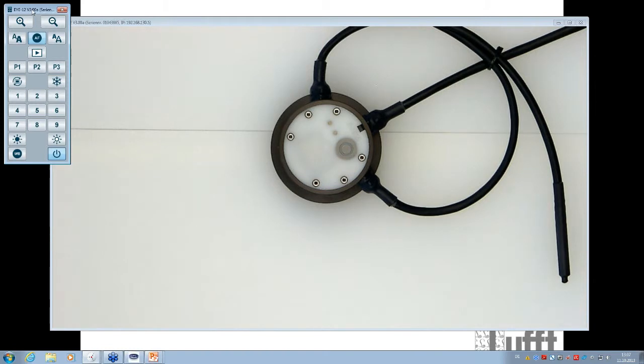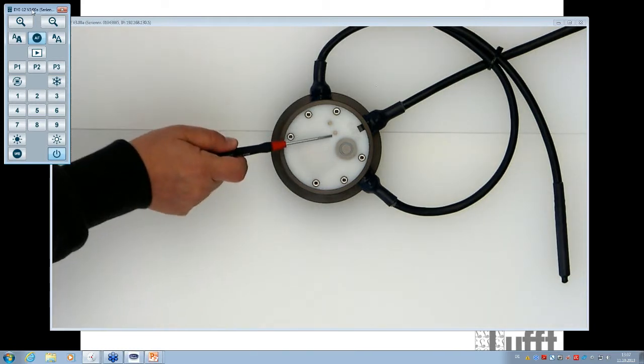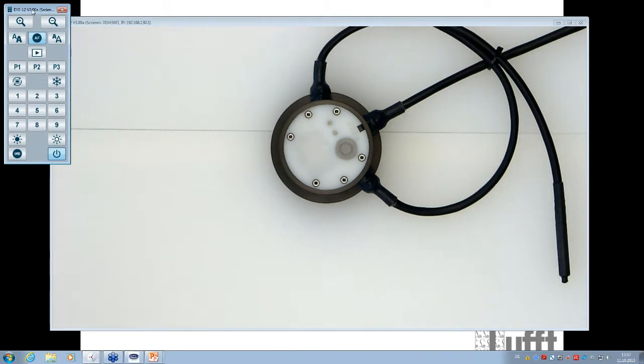So that's really important. What you need to know again is that this conductivity measurement depends on the water film and on the temperature. For example, in the German regulation, which is called TLS, it is said that under 50 micrometers you cannot detect the freezing point. That means, because our radar sensor is really sensitive, if you have a water film of 30 micrometers, you will get no freezing point in this case, because the sensor will start at 50 micrometers to give you the information about the freezing point. That's one thing. So it depends on the water film and it depends on the temperature.